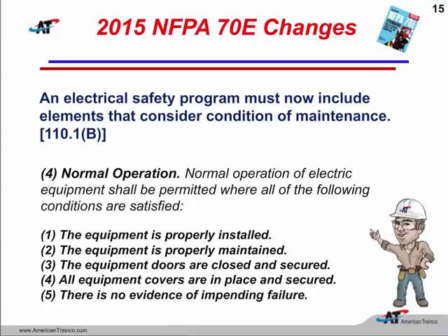Number 3, the equipment doors are closed and secured. Easy to make sure that happens. All equipment covers are in place. That's good. No evidence of impending failure. So we're going to have to take a little bit of history of the equipment. Has there been some arcing involved over the years?